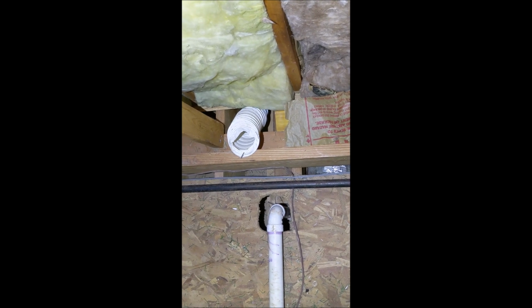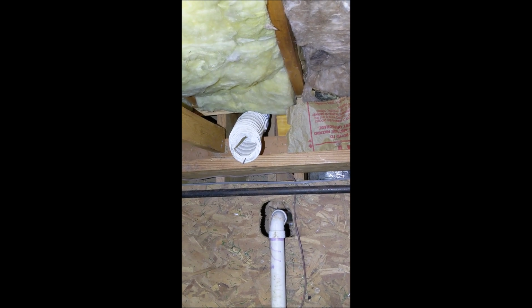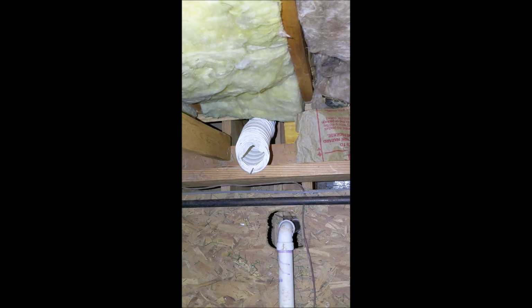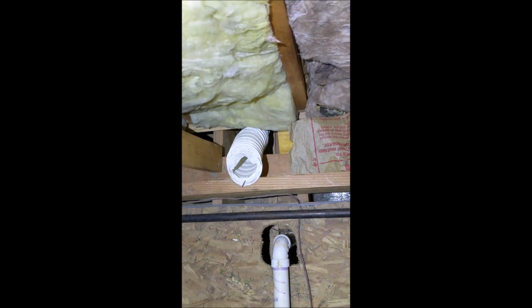So here's a bath exhaust fan. It vents into the attic. All the other ones seem to vent outside. So we do recommend taking this little white duct. Actually, I don't care for the plastic. The solid metal is better. And then extending that out to the eaves, so all that moist air from the bathroom can be discharged outside. Just make sure all the insulation stays in place, especially at the walls.